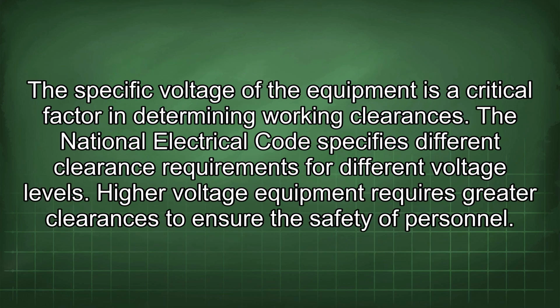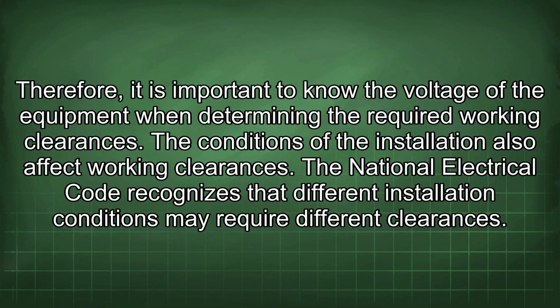The specific voltage of the equipment is a critical factor in determining working clearances. The National Electrical Code specifies different clearance requirements for different voltage levels. Higher voltage equipment requires greater clearances to ensure the safety of personnel. Therefore, it is important to know the voltage of the equipment when determining the required working clearances.